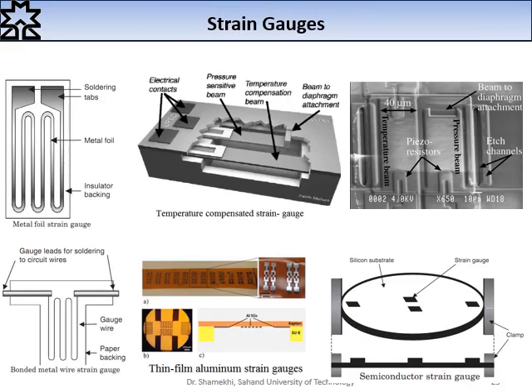In this slide, some applications of strain gauges have been shown. As you can see, some strain gauges are like a metal foil strain gauge, some metal foil on a backing. Also some temperature compensated strain gauge. As you can see here, we have a strain gauge sensor with two elements. The first one is the main sensor, connected to the diaphragm. We have a diaphragm here, as you can see.